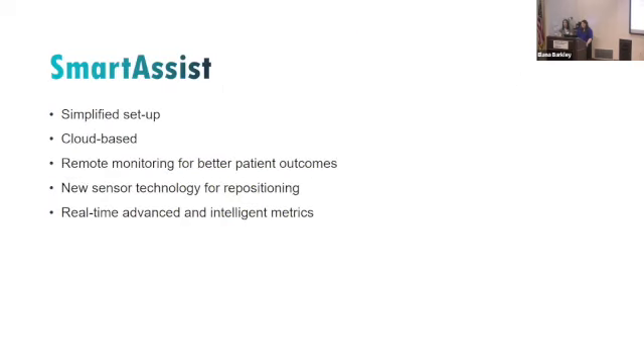All right, so I've been saying Smart Assist after every Impella, so they have something called Smart Assist. It's a cloud-based program for the Impella. It simplifies the setup of the Impella device. It allows for remote monitoring for better patient outcomes. So if advanced practitioners are at home and they want to check on their patient and see how they're doing, they're able to log in and see the numbers and what's going on with the device at the time. It's also good if you're having issues with your pump. So the Impella rep can log in, look and see what's happening. If you're having suction alarms, they can help you troubleshoot.